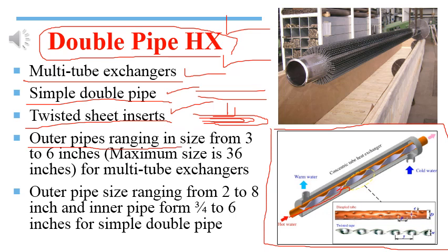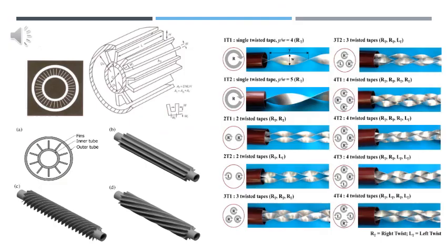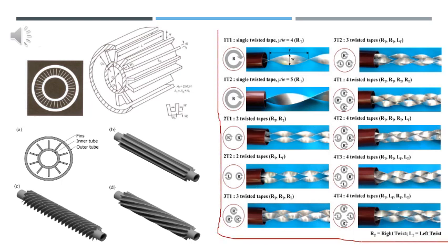Some key specifications: the outer pipe ranges from 3 to 6 inches in size, with a maximum of 36 inches for multiple tube heat exchangers. For the simple double pipe heat exchanger, the inner pipe ranges from 2 to 8 inches and the outer pipe from 3/4 to 6 inches. There are several types of twisted sheet arrangements, and the length and surface area of the twisted sheet can be calculated using formulas in textbooks, though calculations are more complex and lengthy.